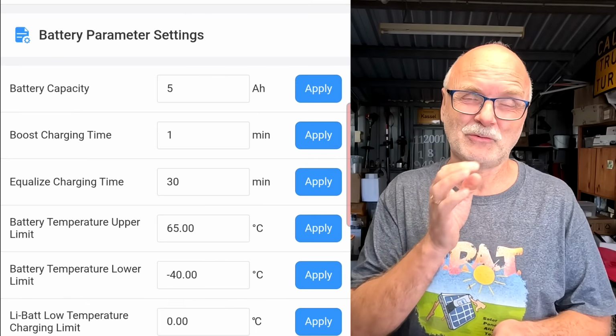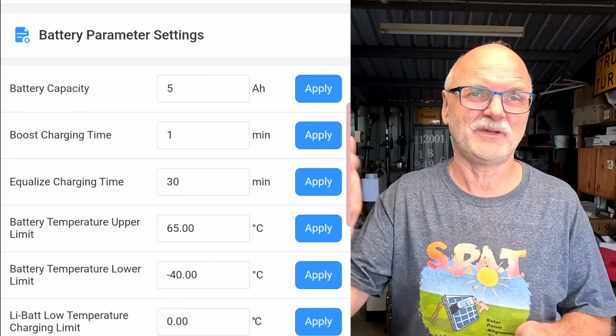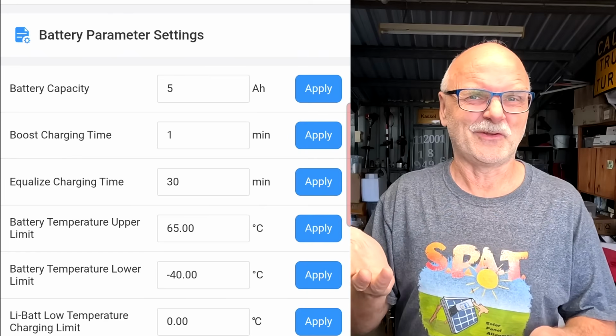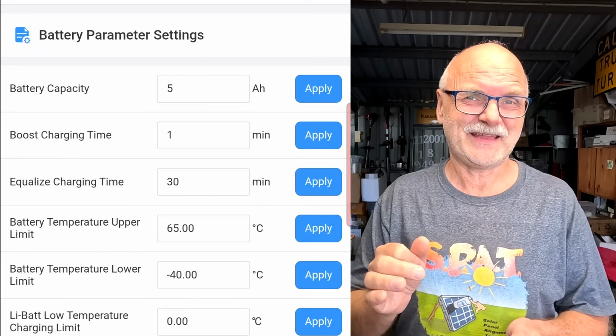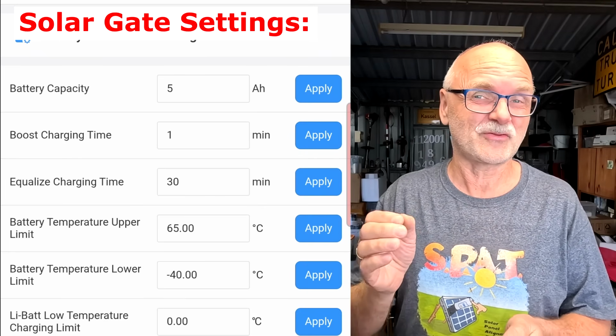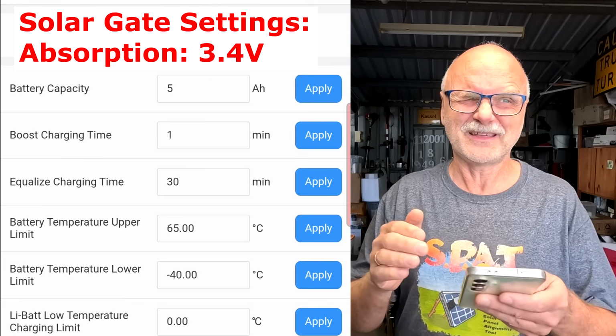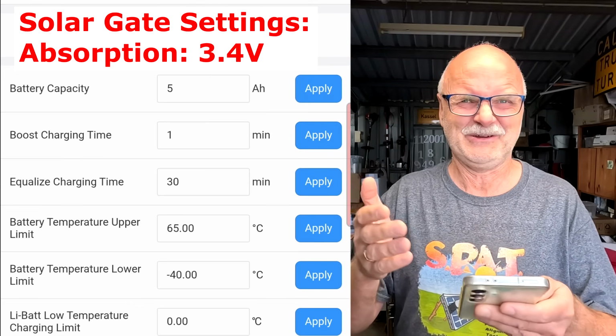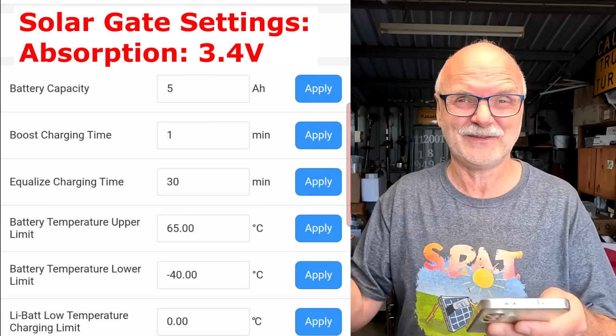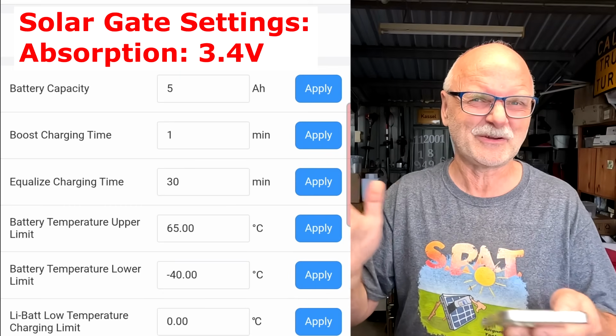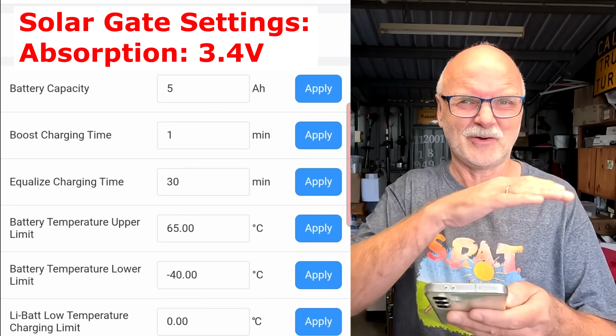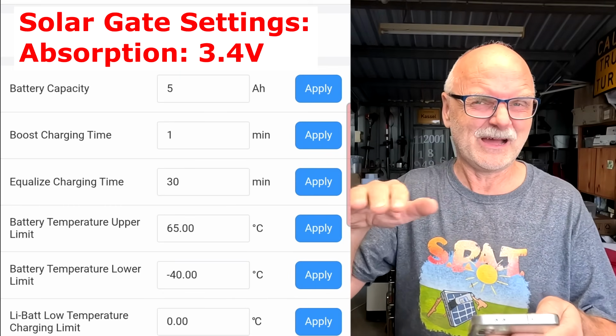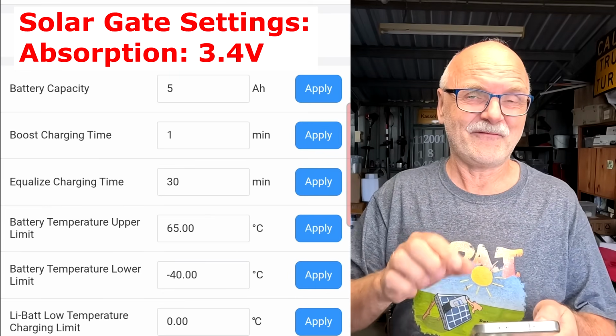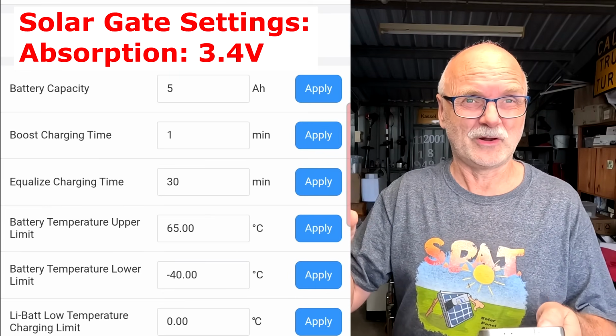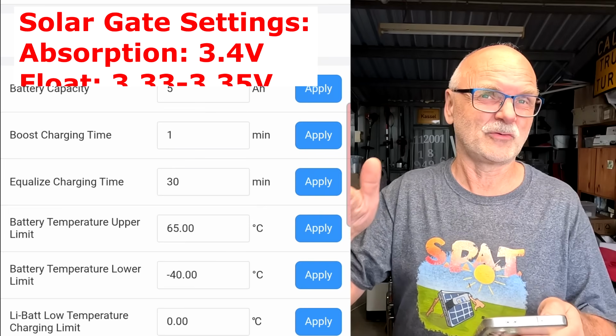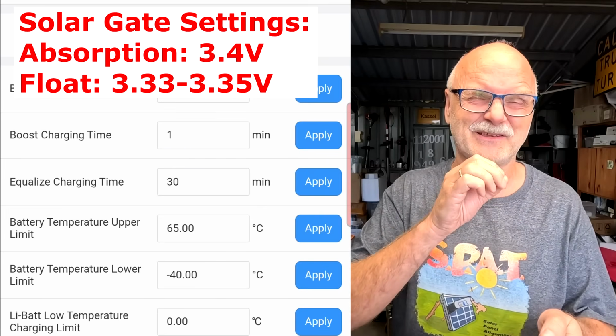Especially in the solar setup, I don't want to fully charge the battery every single day - it's just not necessary. So I'll probably set my absorption voltage to only 3.4 volts, giving us somewhere between 85 and 95% state of charge. It will be inconsistent because we're still operating in the flatter area of the charge curve. After half an hour at 3.4 volts per cell, we drop down to 3.35 or even a bit lower maybe.